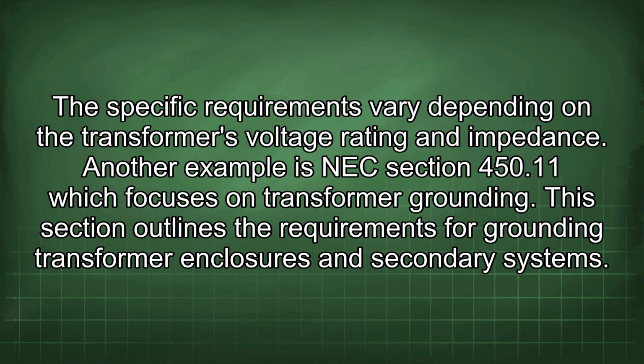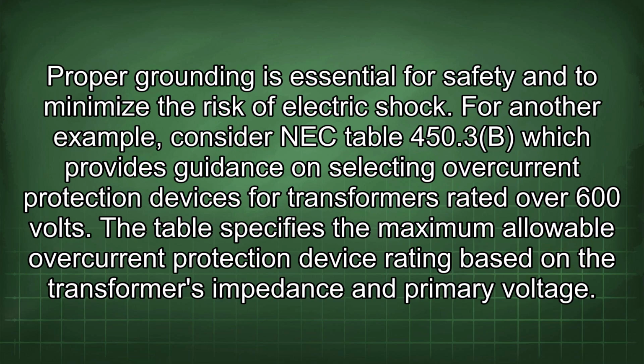Another example is NEC Section 450.11, which focuses on transformer grounding. This section outlines the requirements for grounding transformer enclosures and secondary systems. Proper grounding is essential for safety and to minimize the risk of electric shock. For another example, consider NEC Table 450.3(b), which provides guidance on selecting overcurrent protection devices for transformers rated over 600 volts. The table specifies the maximum allowable overcurrent protection device rating based on the transformer's impedance and primary voltage.